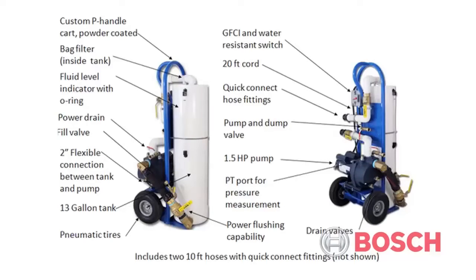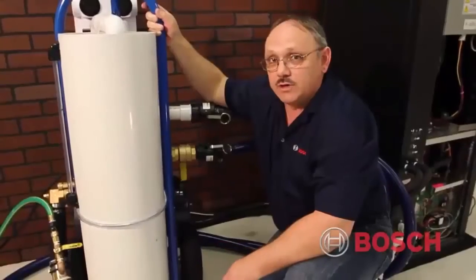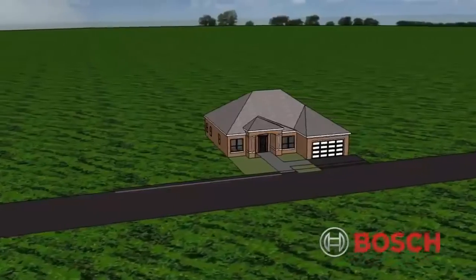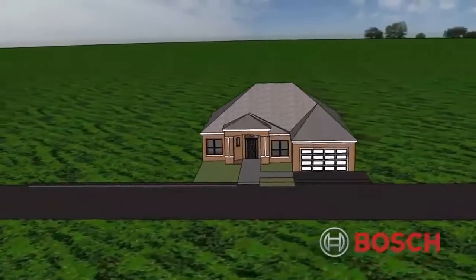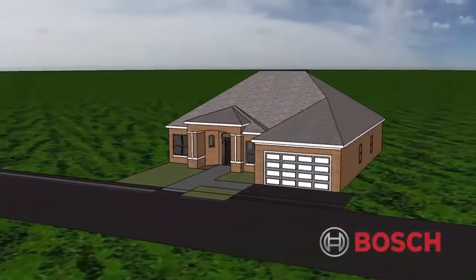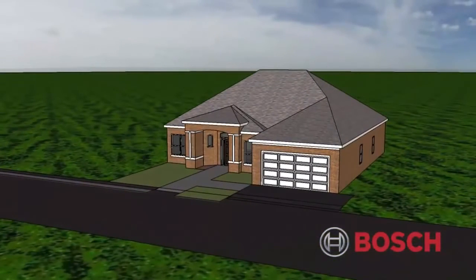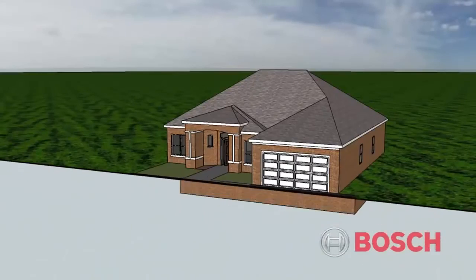It is 120 volt. It also has a reservoir tank on it and a series of valves that allows us to fill this reservoir, pump water through our loop system, and flush all the debris out and purge all the air out of the system. For this system, we'll be using a water-only solution because this installation is in a southern climate and the minimum entering loop temperatures never drop below 42 degrees Fahrenheit.